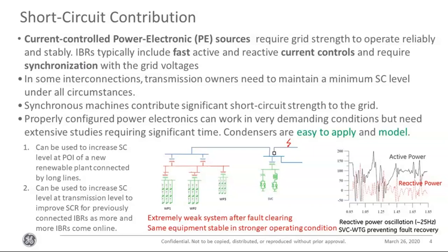Now, this same setup was stable in a stronger grid condition, in a stronger operating condition. That is not to say that increasing the short circuit ratio is the only way to deal with these weak grid issues. Properly configured power electronics are very powerful and they can work in very demanding conditions, but they need extensive studies that can require a lot of time.